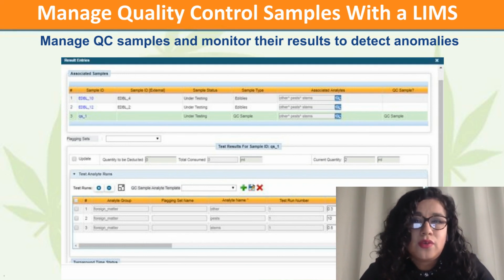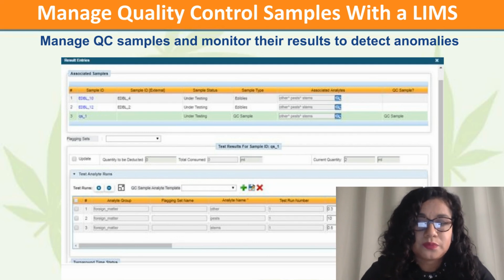If there is a question regarding the validity of a test result, say there is a pesticide, for example, beyond the acceptable limit, you can show that your spike QC sample with a known concentration of pesticide was accurately quantified. So you can assure that if the pesticide was present in the test sample, it would have been detected. It also ensures that the potency is correct. If you say the THC level is 15%, it is, and you know this because the QC sample was able to correctly identify the THC concentration.